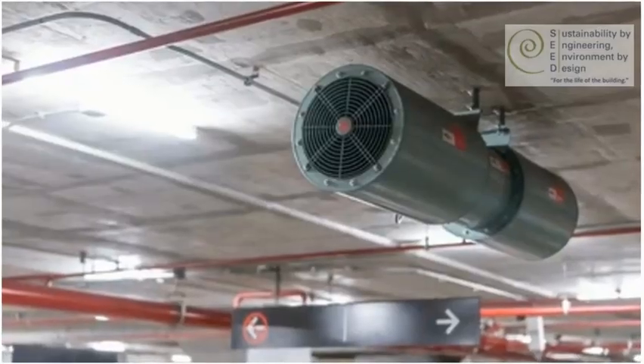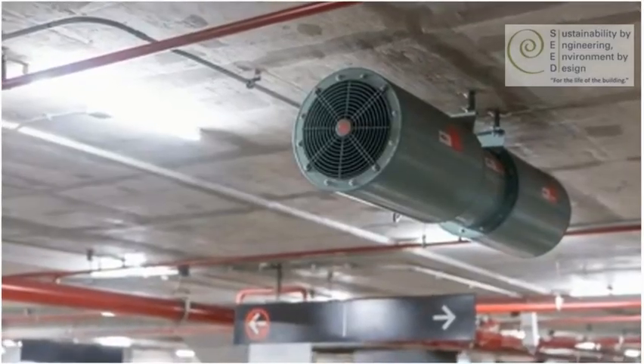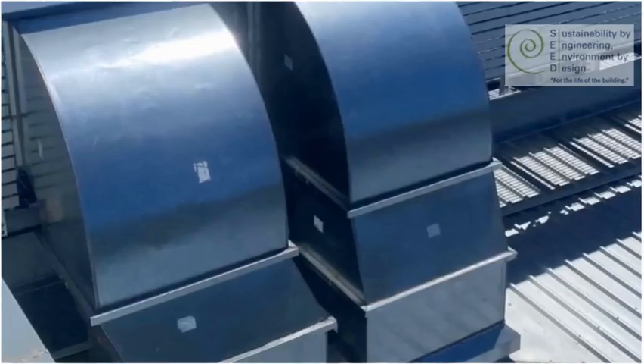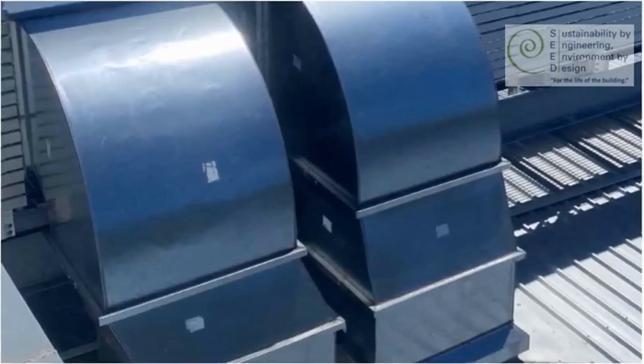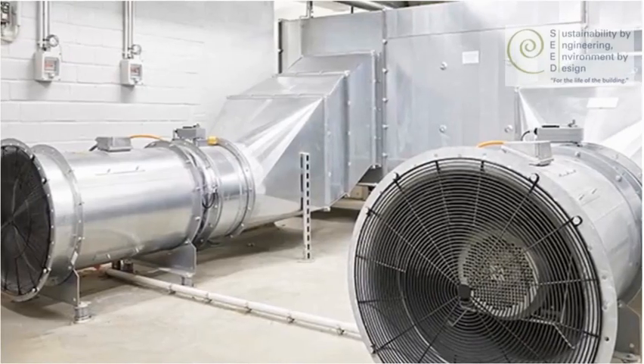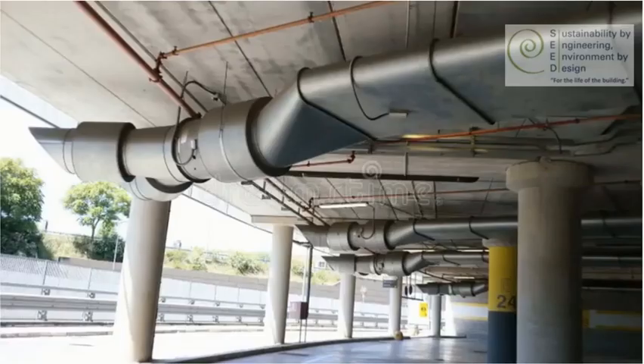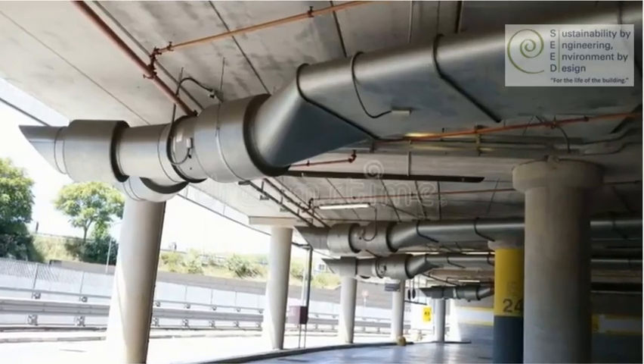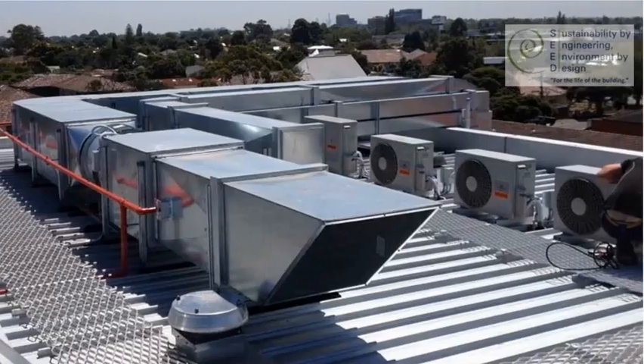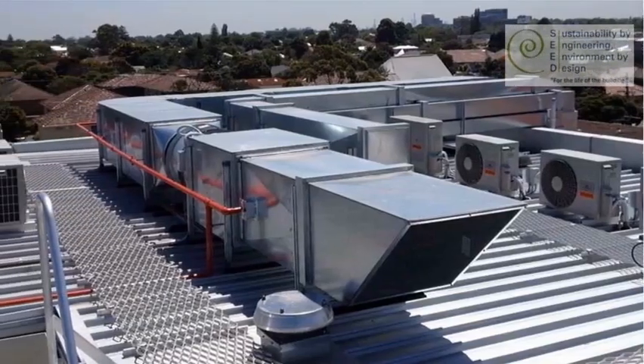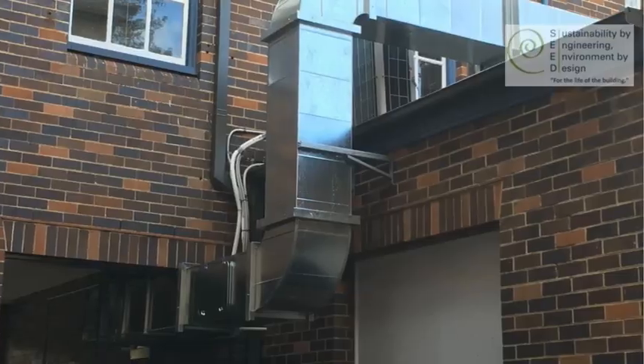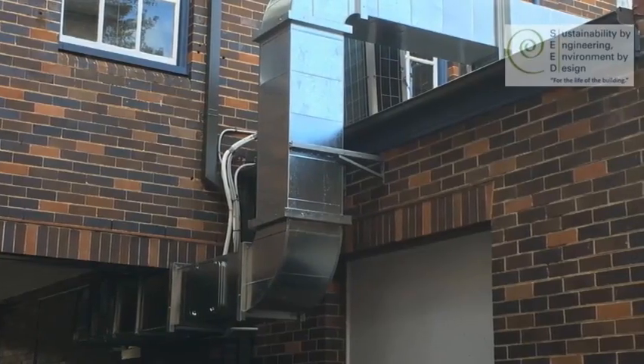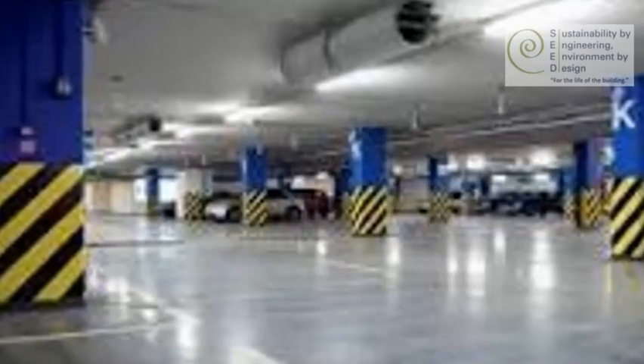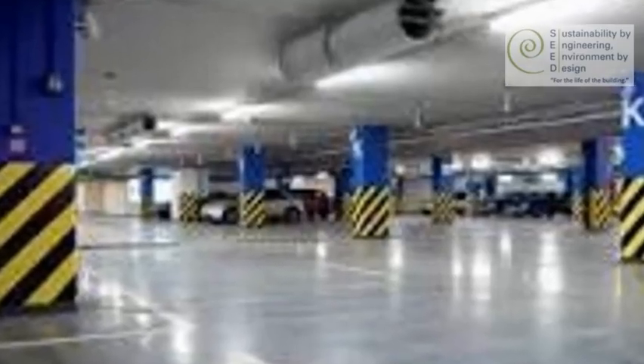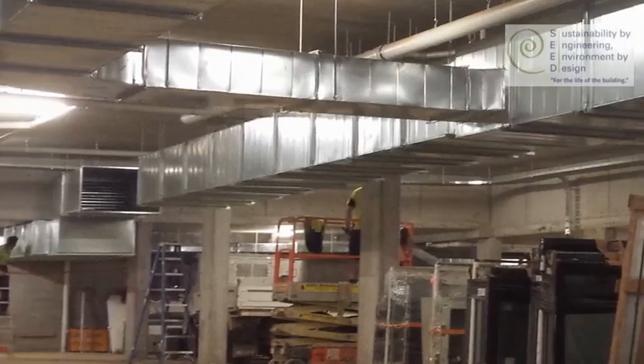There are new systems that tempt us with their ease, but they often require extra systems to be supplied, new plant rooms in unusual locations, or discharge issues or duct height issues. Then we get to the roof where we need to discharge, and we find we've got the route to the roof to consider, the risers, and all the time we need to satisfy our certifier that we are compliant.